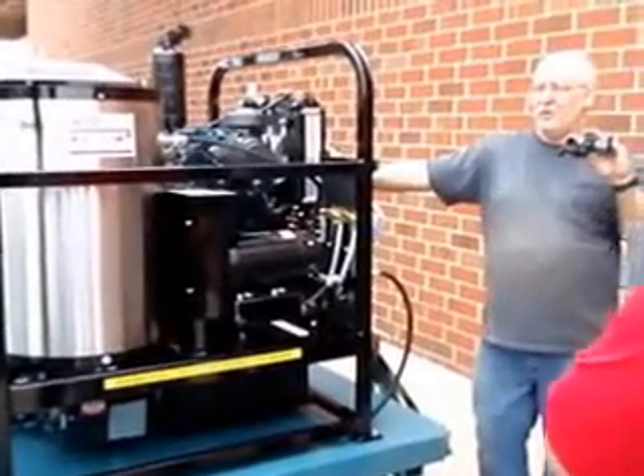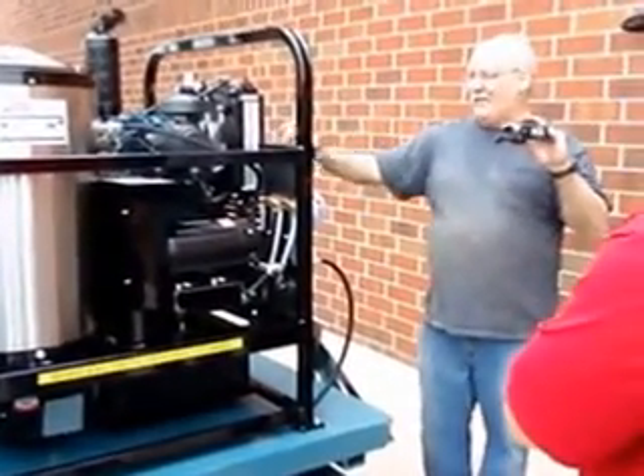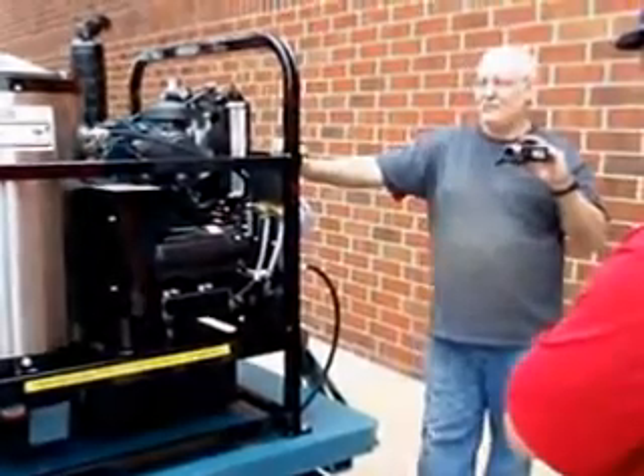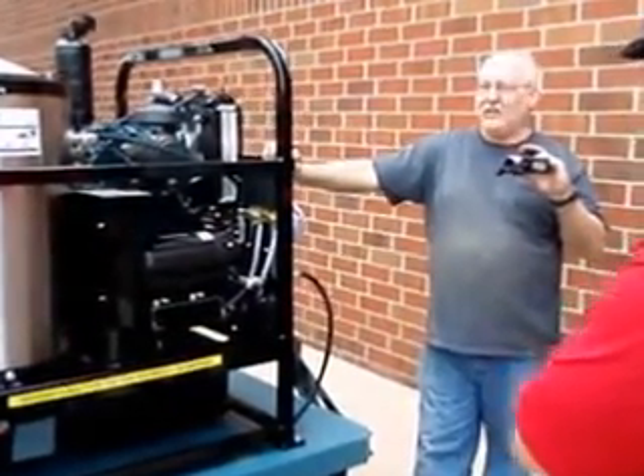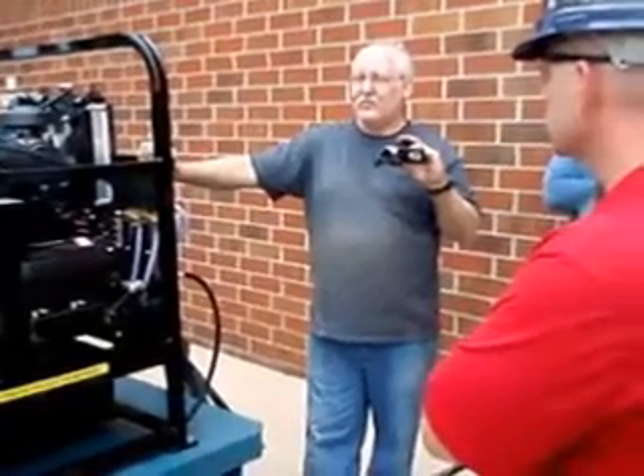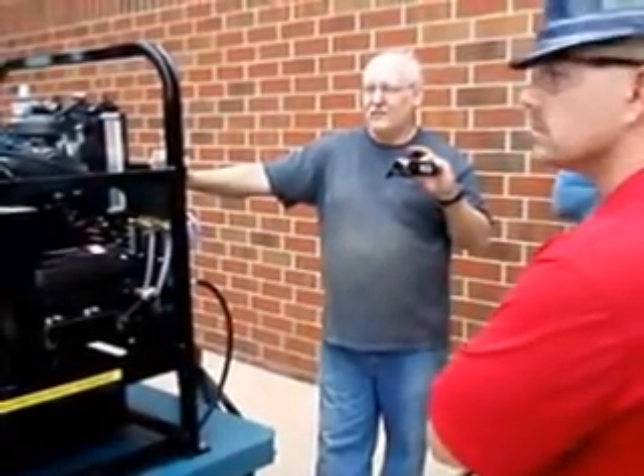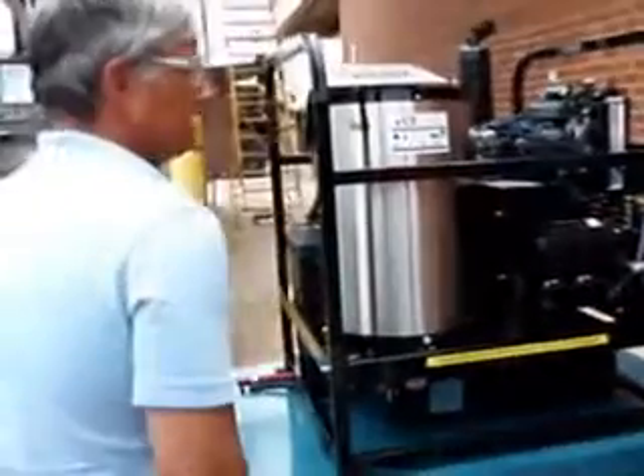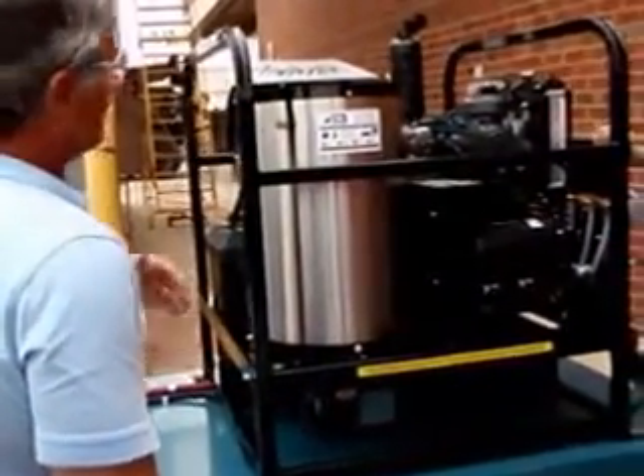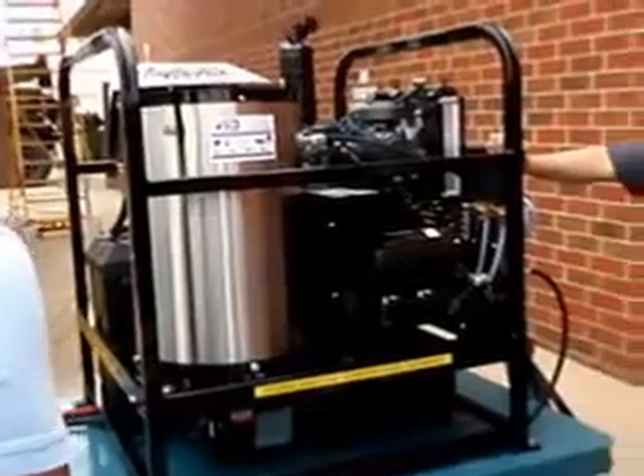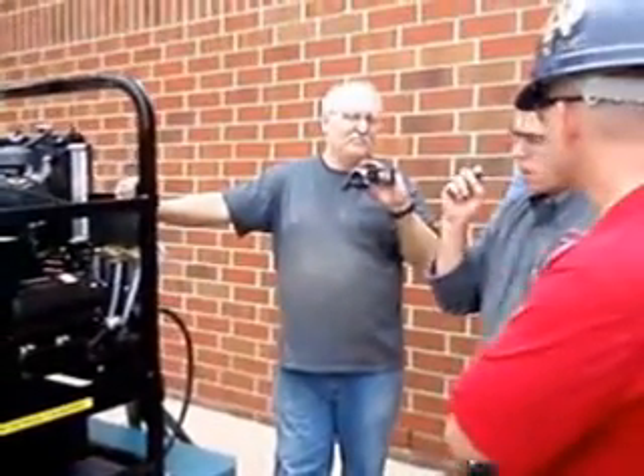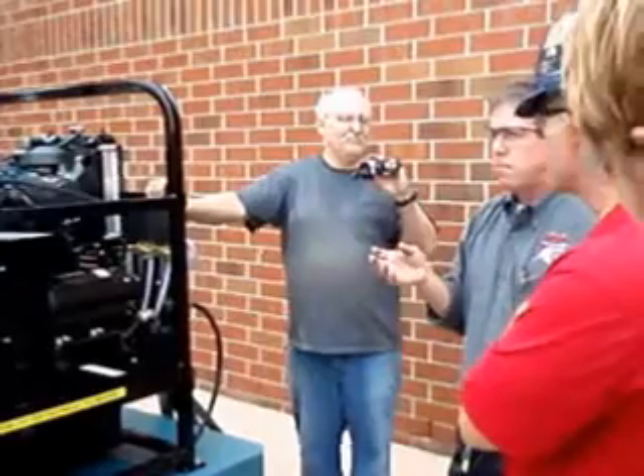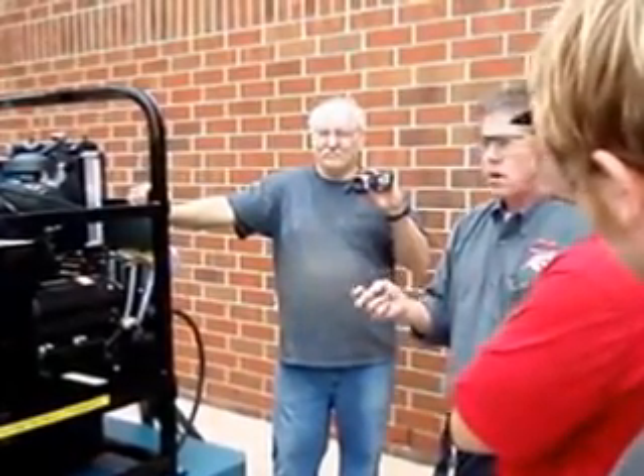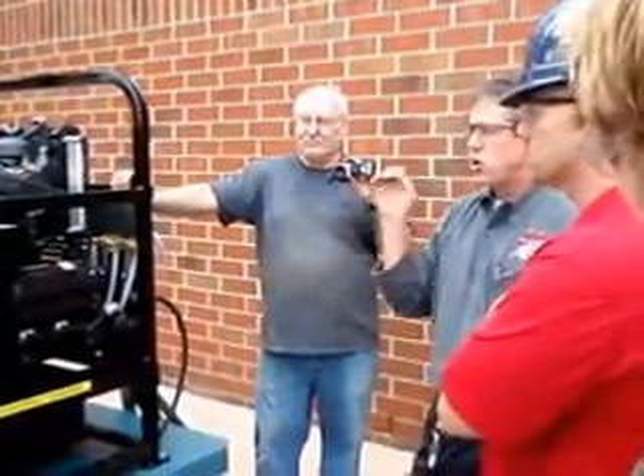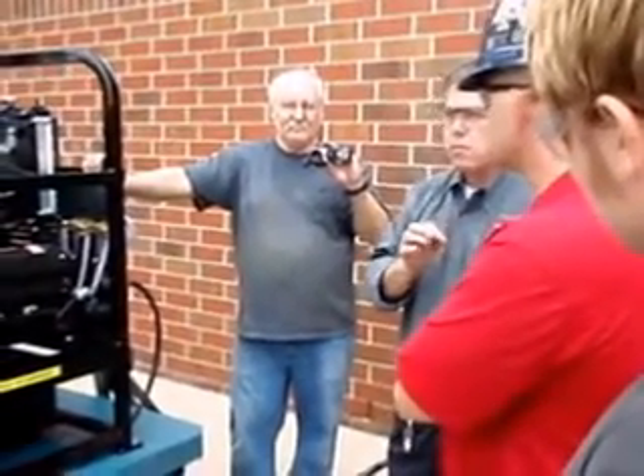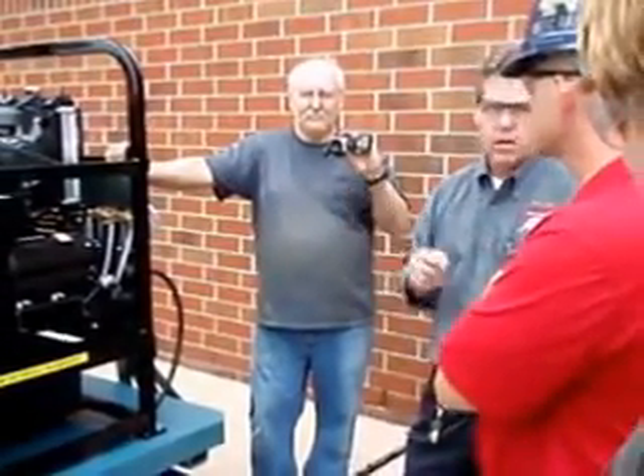I've been told that the DC burners aren't as efficient as far as their light when they light off. The AC ignition is a little better, so it reduces the amount of soot. That's right. Is there a recommended cleaning interval on these, like every 500 hours from a soot standpoint? No, sir. Your burner system, unless there's a problem, should not soot. Okay, so if it starts burning dirty and you're starting to see smoke, there's a problem. You shouldn't see smoke out of these systems.